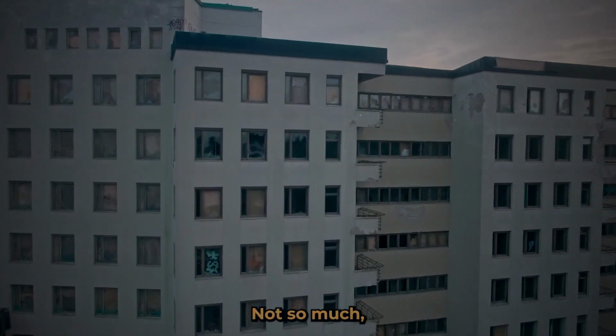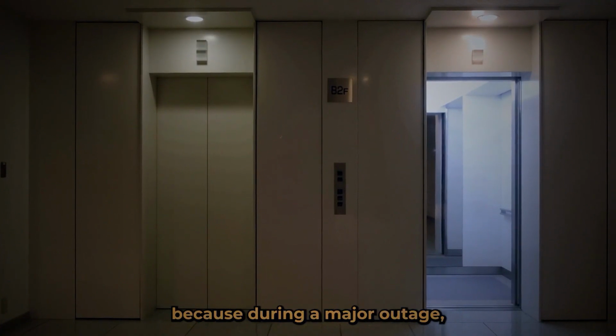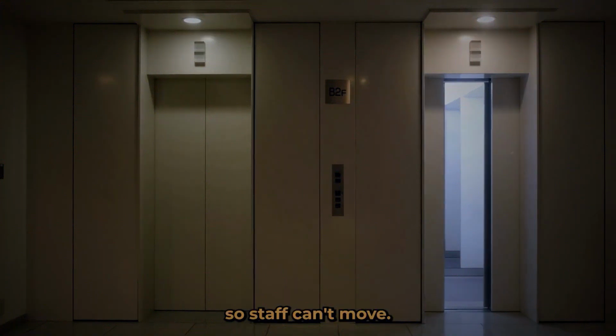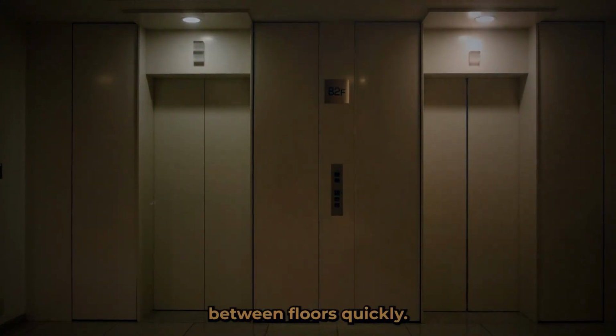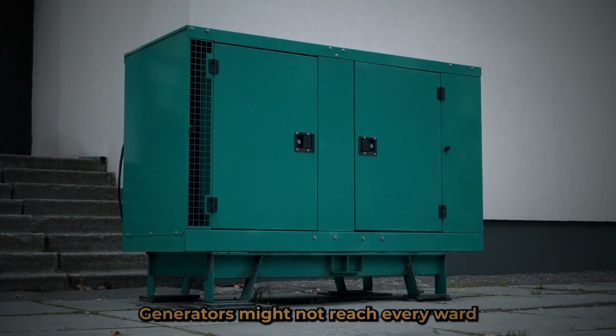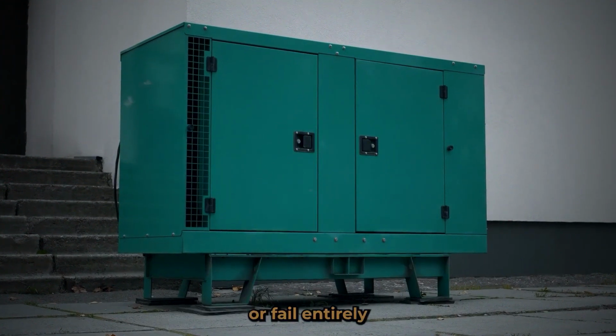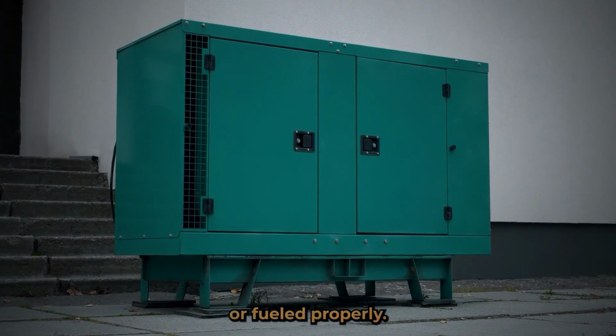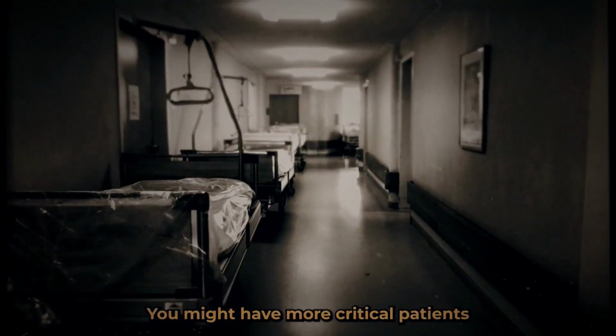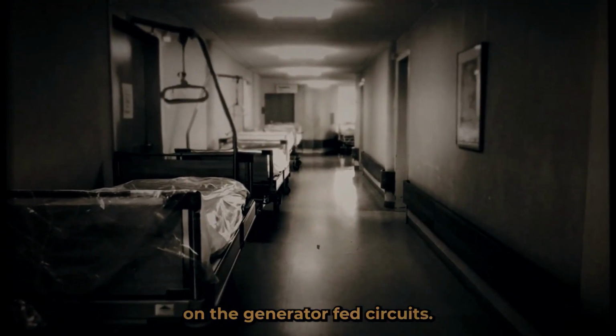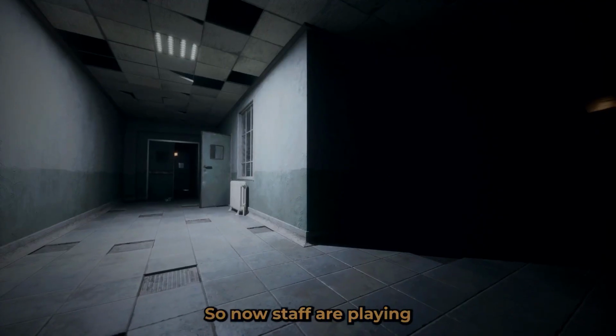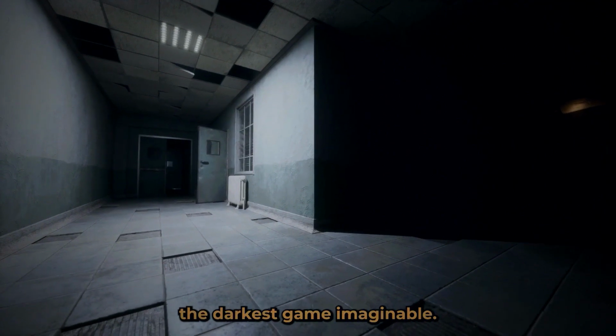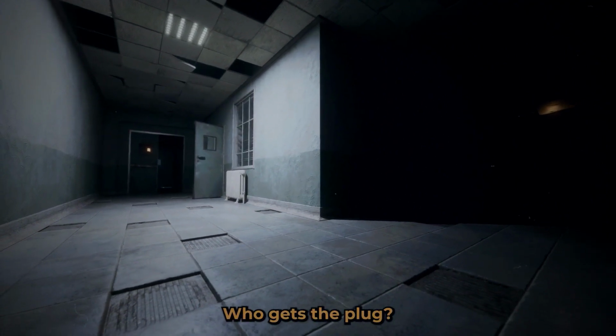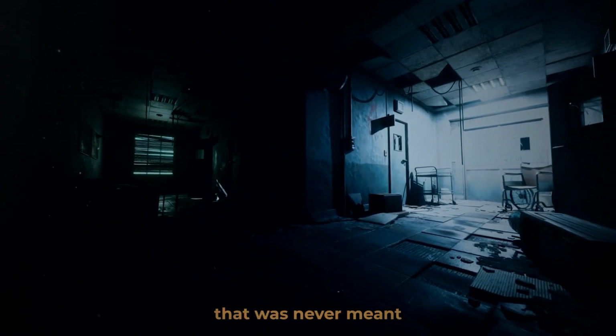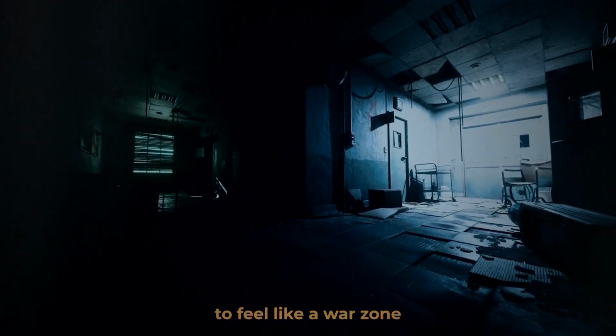Not so much. Because during a major outage, elevators might be dead, so staff can't move ventilated patients between floors quickly. Generators might not reach every ward, or fail entirely if they weren't maintained or fueled properly. You might have more critical patients than you have outlets on the generator-fed circuits. So now staff are playing the darkest game imaginable. Who gets the plug? This is where hospitals start making battlefield decisions inside a building that was never meant to feel like a war zone.